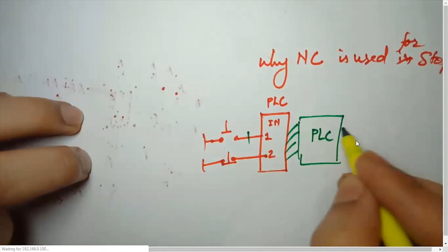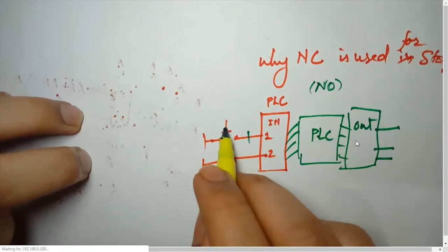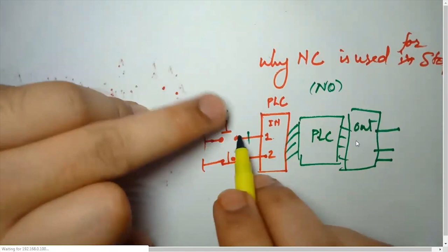To begin with, what will happen if the wire is cut from here? Will my PLC indicate that a fault has occurred? That is not possible if my button is NO type. If the stop is NO type and someone tries to press it, no signal will go to my PLC, and one won't be able to stop my logic. That is a very risky kind of design.